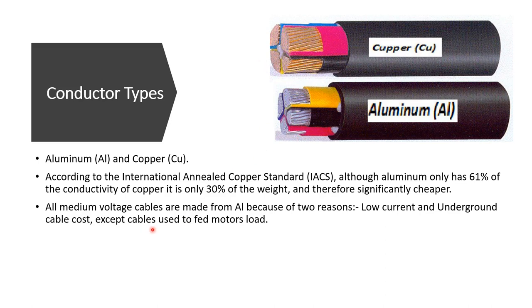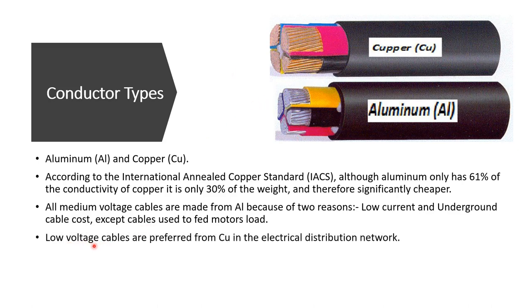Copper cables are used to provide current to loads in medium or low voltage networks because higher conductivity produces lower voltage drop, which means nearly the same voltage at the motor terminals, providing the required torque. Low voltage cables are usually made from copper, while aluminum is typically used in medium voltage and overhead high voltage transmission lines.